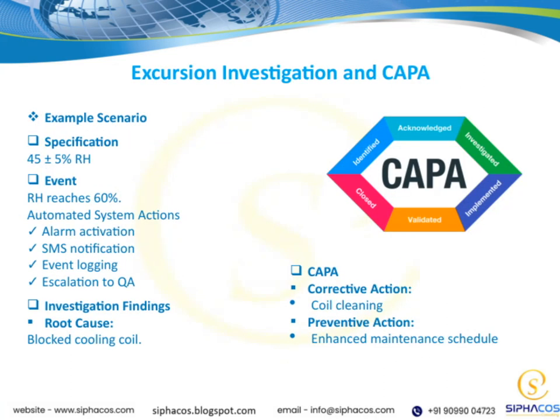Let's look at how we handle deviations through CAPA, that's corrective and preventive action. In this example, the specification calls for relative humidity to stay around 45%, plus or minus 5. But when it hits 60%, the system kicks in: alarms sound, notifications go out, and quality assurance gets alerted. The investigation reveals the root cause, a blocked cooling coil. The corrective action is to clean the coil, while the preventive step updates the maintenance schedule to keep this from happening again.